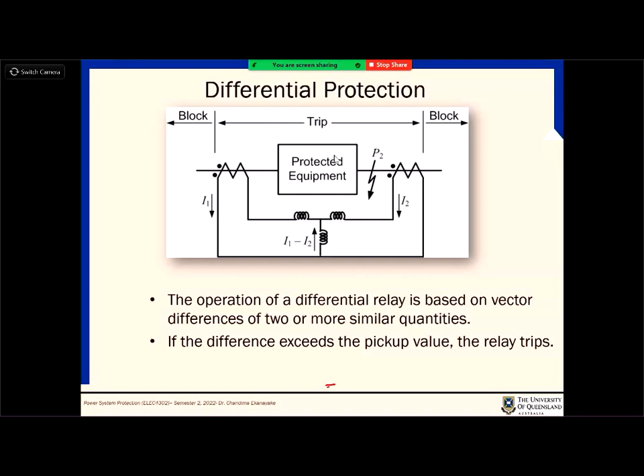So mainly they are used for these sort of electrical equipment, and you compare the input and output currents. One of the important things here is that to measure that current, you can't just put an ammeter somewhere here. Your measuring circuit should be isolated from the power circuit. So that's why you need to put a current transformer here and another current transformer on the other side, and then you measure that current in the secondary circuit. The primary circuit is the one to which the equipment is connected. The secondary circuit is the circuit where the CT secondaries are connected.